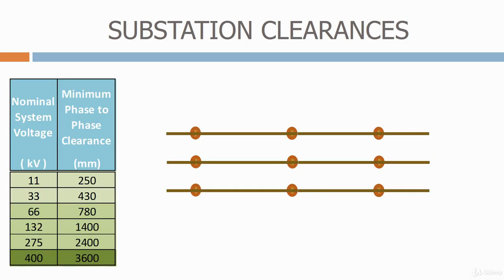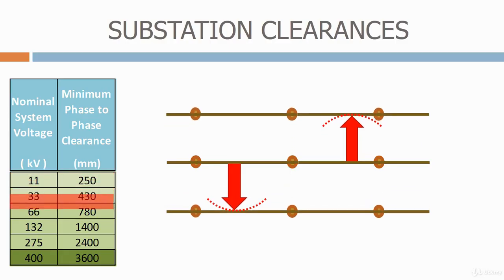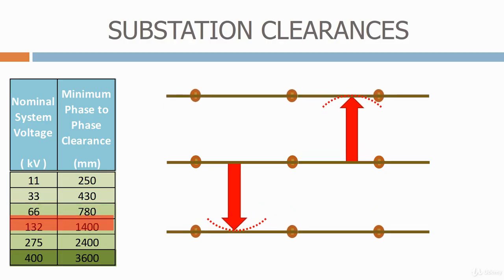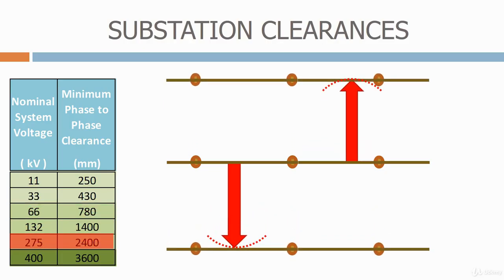Here we have a typical bus bar supported by post insulators. Assuming this is a three-phase bus bar, the distances between the bus bars will depend on the phase-to-phase clearance. For 11 kV, the distance will be 250 mm. As we increase the system voltage, the distance between the bus bar also increases. At 275 kV, the distance will be at least 2.4 meters. You will see this distance applied throughout the air-insulated substation, and all the bus bars and equipment will have the same minimum distance between the live conductors.